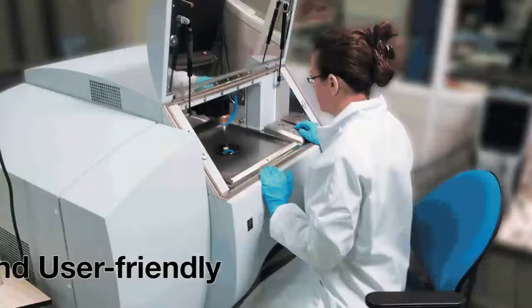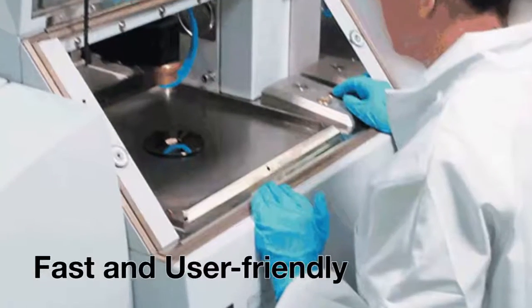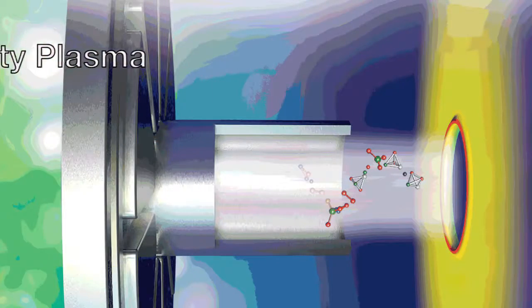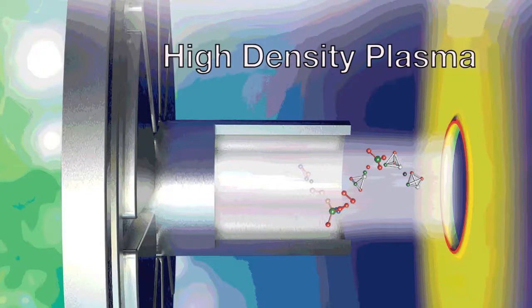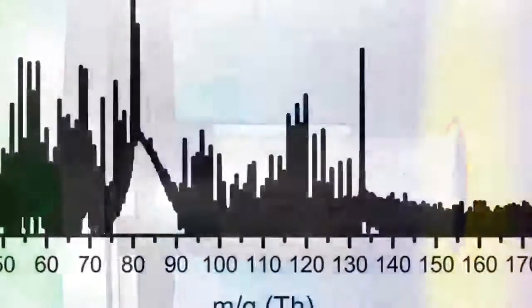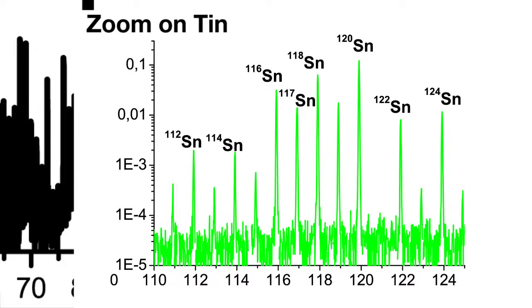PPTOF-MS is a very fast and user-friendly depth profiling tool. First, the sample doesn't need to be transferred into a UHV chamber. Second, the glow discharge is a high-density plasma yielding erosion rates as high as several tens of nanometers per second. And third, the mass analyzer is ultra-fast and non-sequential.